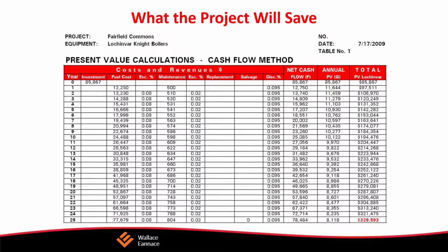Whenever we select a system, one of the things we're looking at is what the project will save. So here's a project that we worked on, Fairfield Commons. We had Lochinvar Knight Boilers. We do a present value calculation, looking at the cash flow method, and see what happens over the life cycle of the unit over the next 25 years. We look at what the cash flow is, what the present value is, and what the savings are.